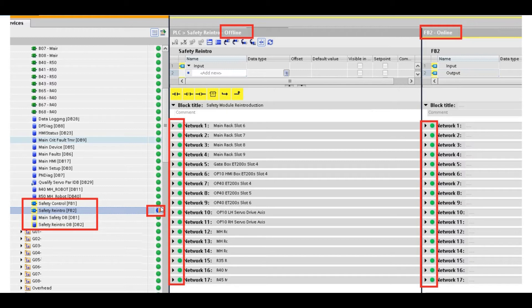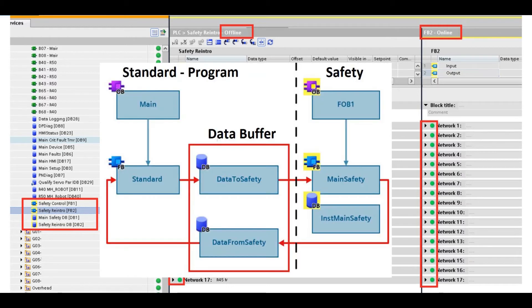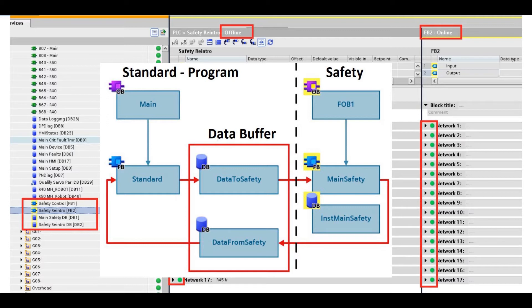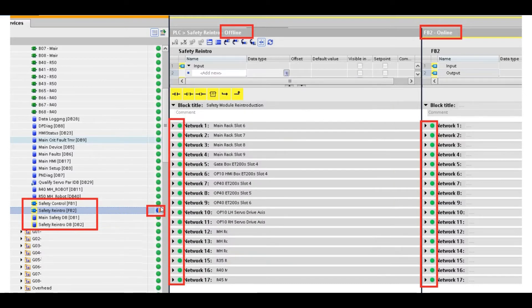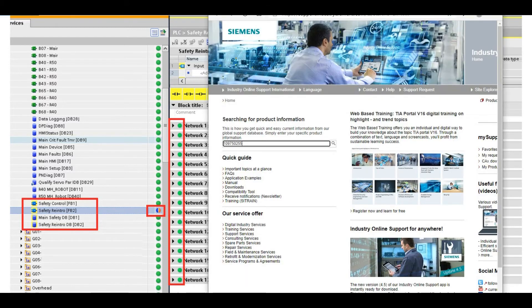To solve this or to prevent this happens, one key method is we need to create one or two interface buffer DB, interface data block. That interface DB plays a role to exchange the data from the standard PLC to safety PLC, or exchange the data from the safety PLC to standard PLC. There's one official document that talks about this.